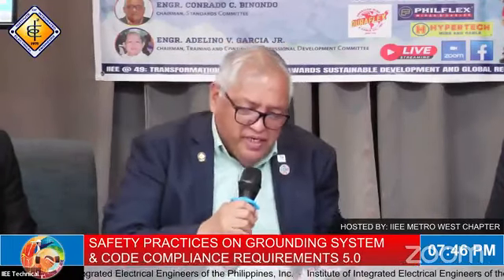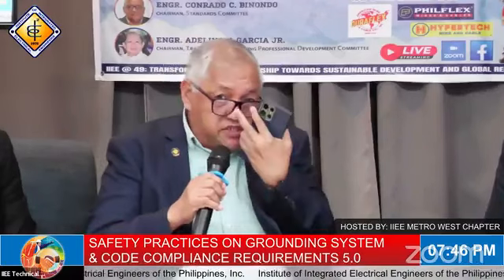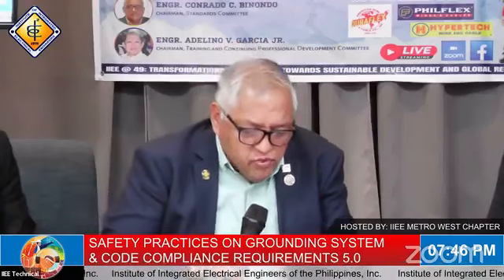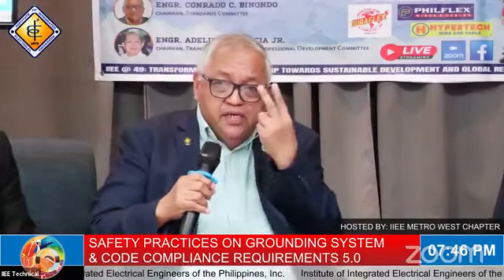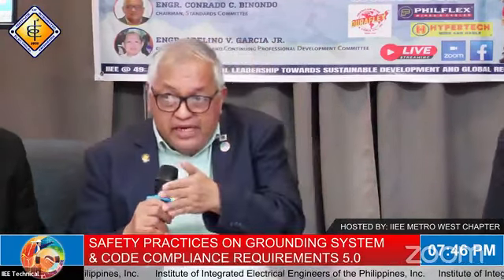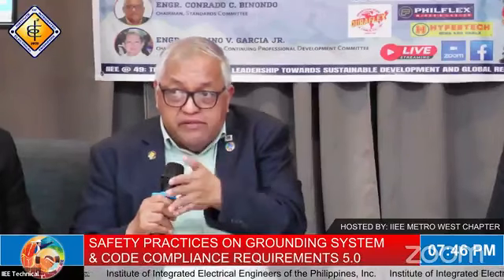Let me direct you now to the 60364 standards when it comes to earthing systems. There are two parts, and it's very long if we tackle it, because in IEC there's what's called system earthing, and another one called the installation arrangement, the earthing arrangement in the installation.